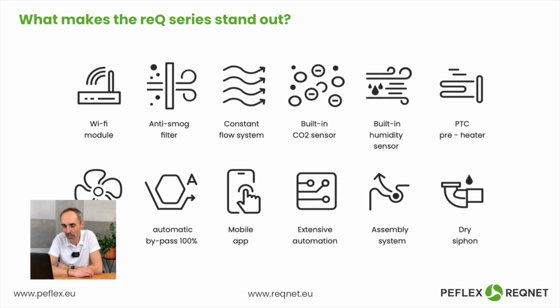And during use, as well as at the very beginning, these 2 streams can differ from each other, because on the supply and exhaust sides, the installations are not the same, meaning they don't have the same resistance. So to correct this, that's exactly what the constant flow module does for us, or during the commissioning process and installation measurements, we would have to make adjustments on the fans. The constant flow module is also useful when the filters get dirty, because dirty filters create additional resistance, which the constant flow module overcomes, maintaining both air streams, supply and exhaust, at the same level.